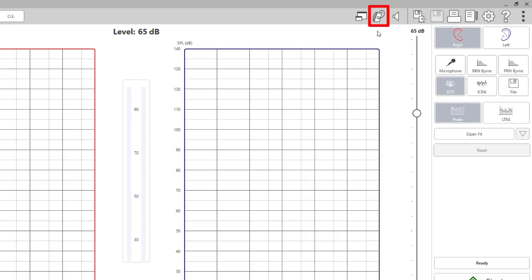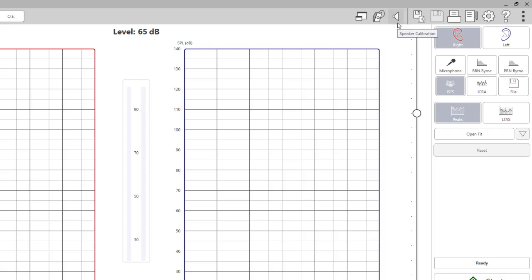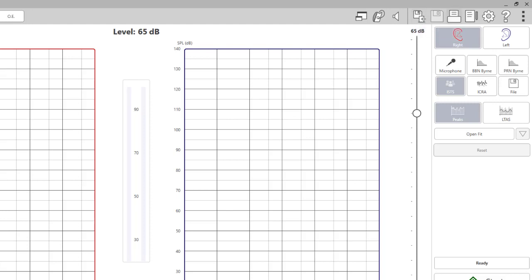Click on the probe mic icon to calibrate your probe tubes. You can now calibrate probe tubes binaurally in studio. The speaker icon is where you will go to calibrate your speaker or speakers. For best practice, speakers and probe tube calibrations should be completed on every patient. Calibrations will be reviewed in the REM and LSM training videos. The next two icons are options to save sessions and exit. These options will be discussed in the testing portion of the training videos.